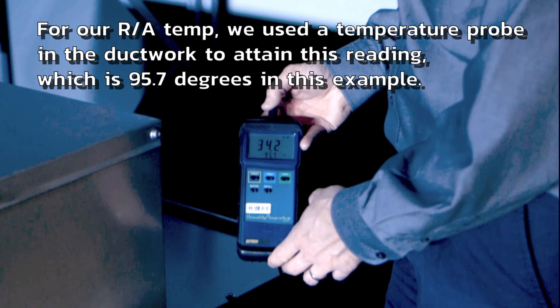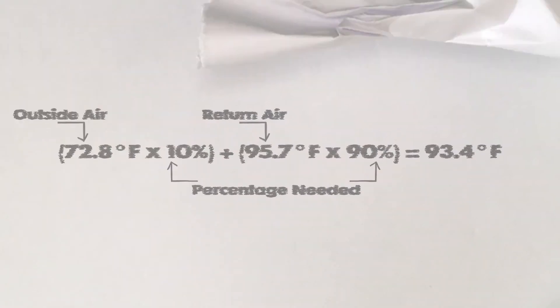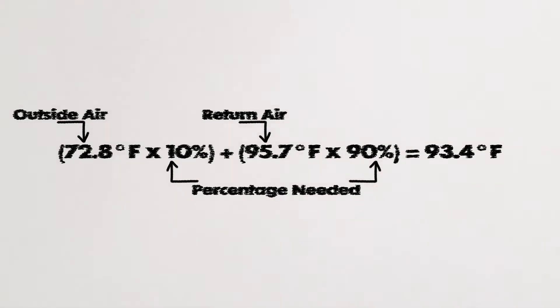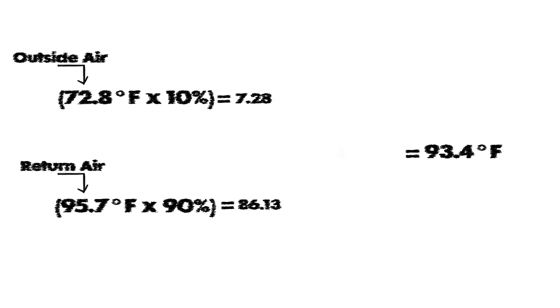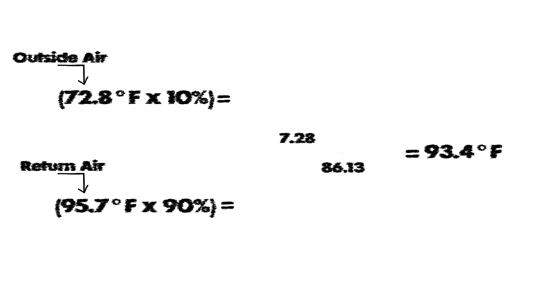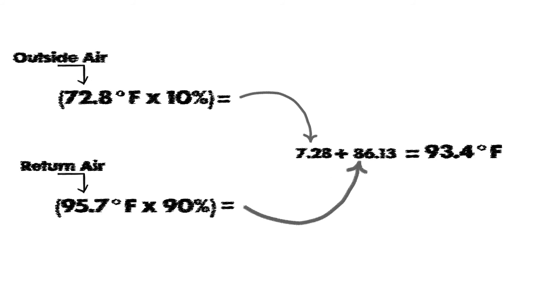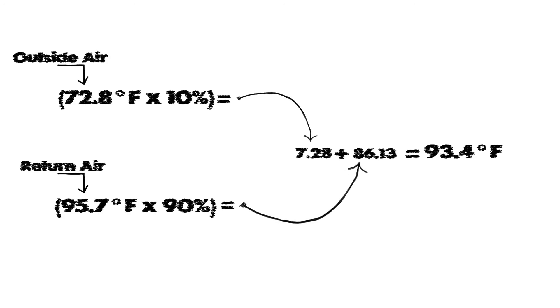Using our readings we will apply the mixed air temperature formula to determine our target temperature. We take the outside air temperature times the percent required, plus the return air temperature times its percent. So 72.8°F × 10% plus 95.7°F × 90% gives us 7.28 + 86.13, and the mixed air temperature should be 93.4 degrees.